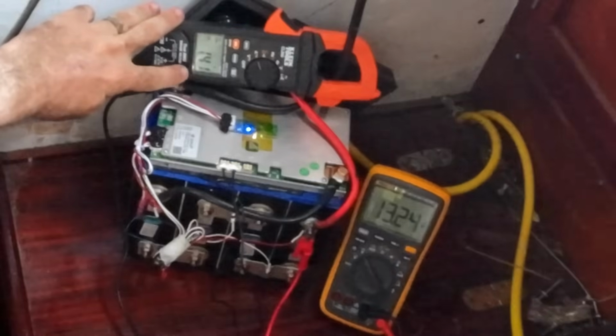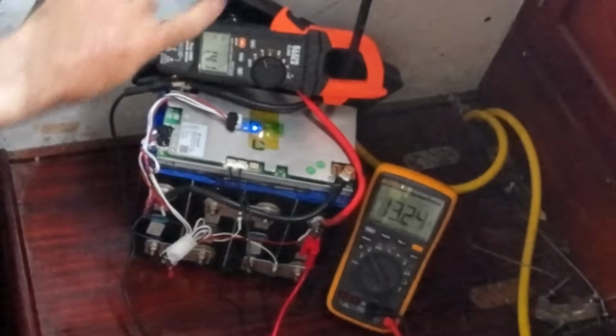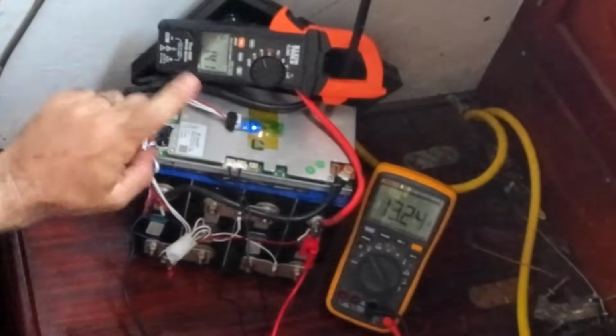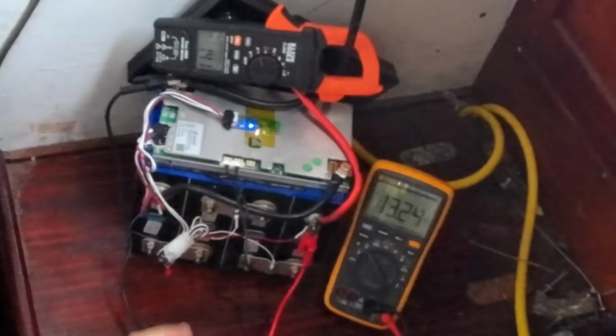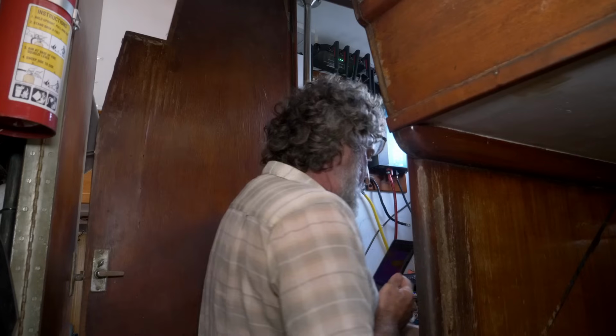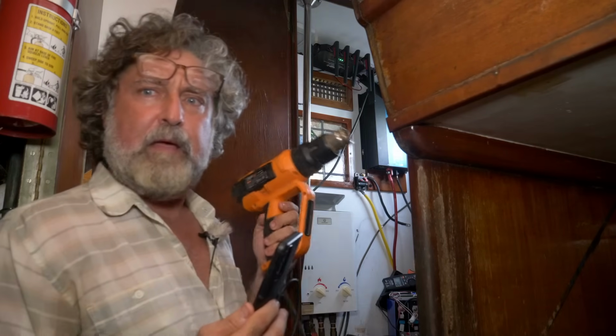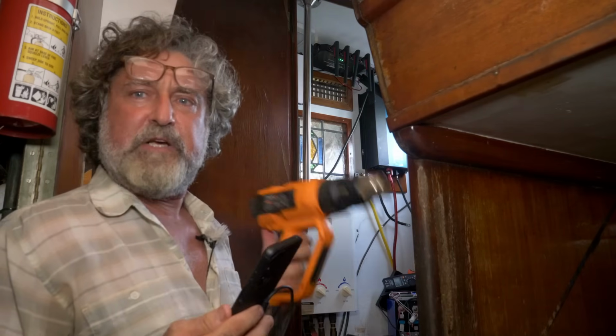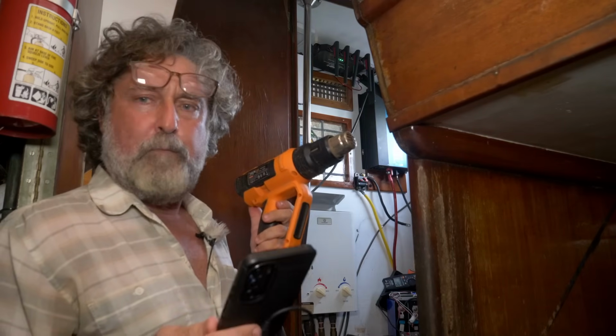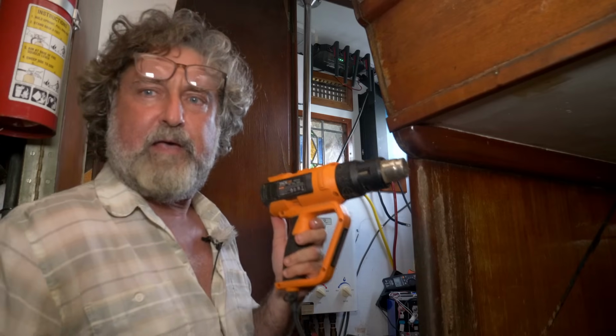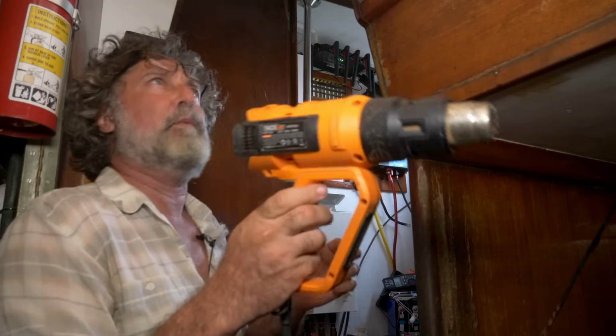This meter is telling us the amps it's drawing, and the inverter just in standby is drawing an amp and a half or so. The battery is at 13.24 volts. I have this heat gun and I can adjust it, so I'm going to adjust it so it draws 100 amps out of the battery, and I'm going to shove it out the window a little bit.